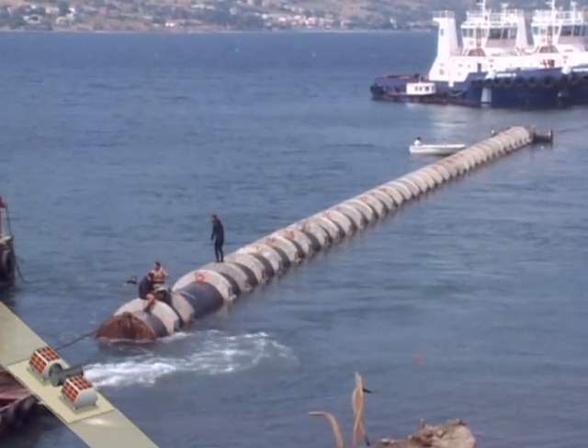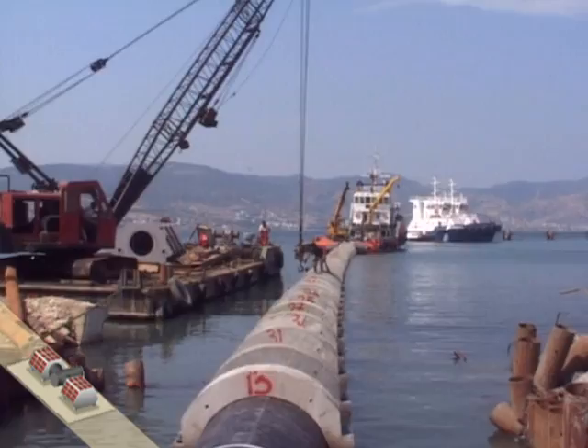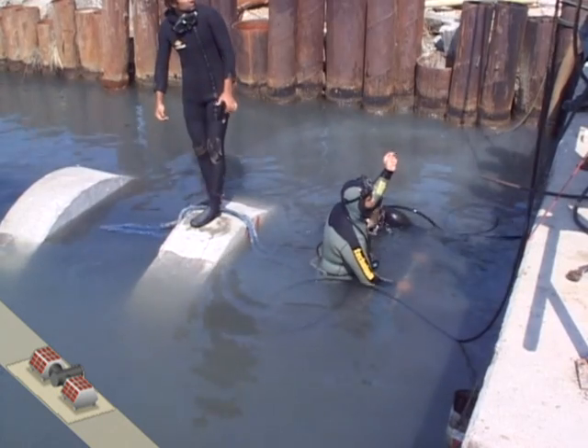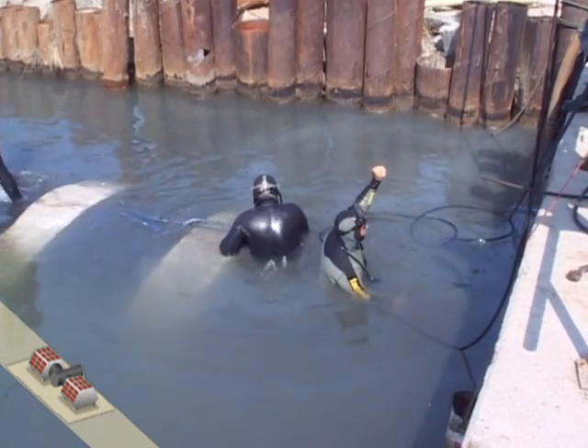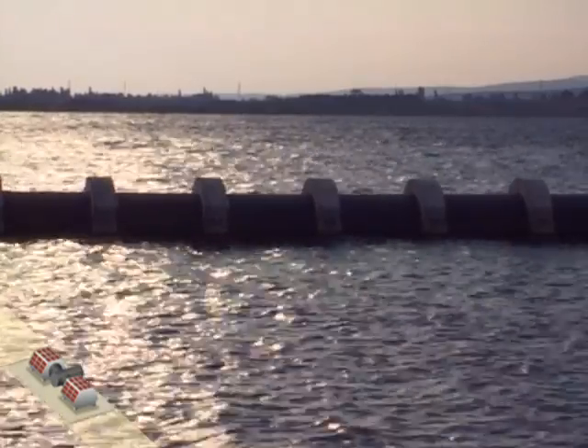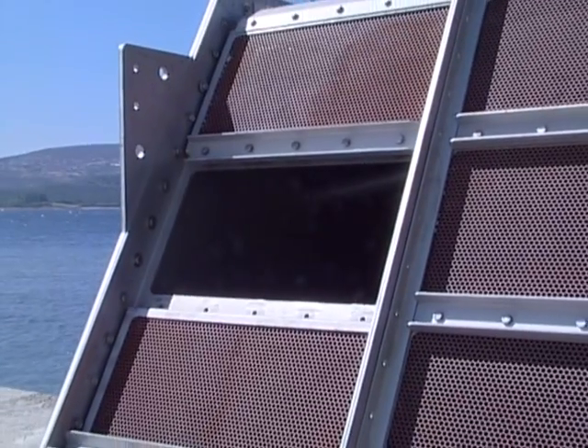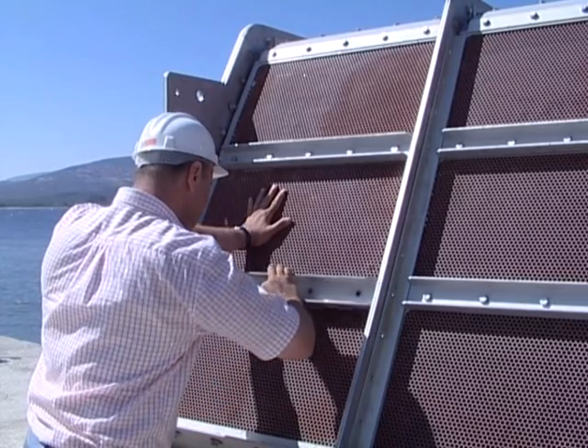Once it is certain that the foundation plate has been positioned exactly, the connecting pipe loaded with concrete rings can be positioned by way of flotation. A team of experienced divers perform the connection of this pipe to the connecting flange of the pump well. The exact timing of submersion and adjustment of the piping is extremely important. One of the striking advantages of TAPAS is the permanent availability of every component, even under operating conditions and underwater, so individual cling-free elements can be separately mounted or exchanged for maintenance without taking the polyhedra completely out of the water.